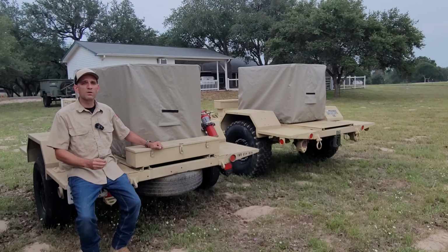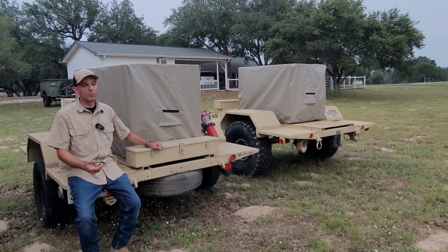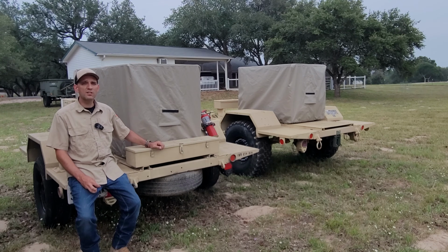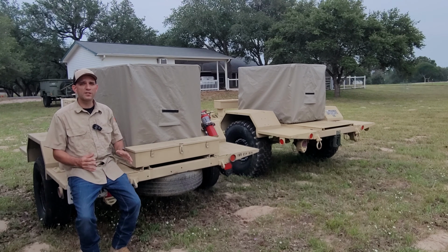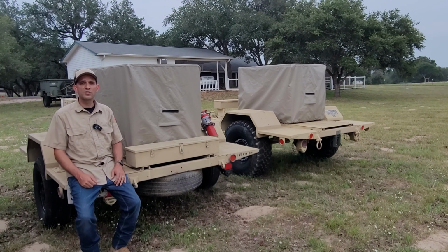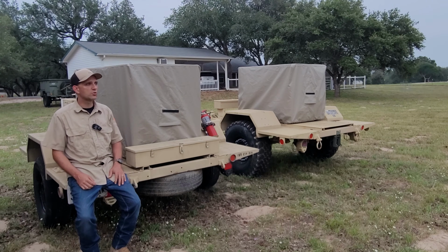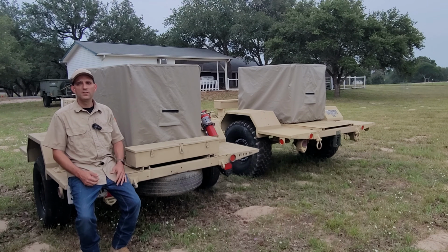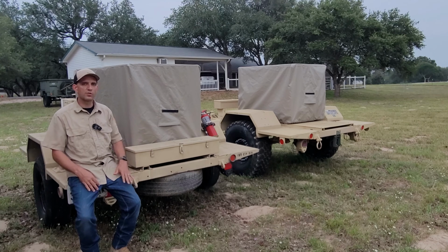So that 6 hour is such a key mark because normally it's going to fail within an hour or two. And the last thing that you want to happen is that failure the first time you go to use this, and you thought everything was good, and at 2 o'clock in the morning you woke up to a hot house or listening to this thing sputter out and diesel fuel leaking all over the ground or something like that.